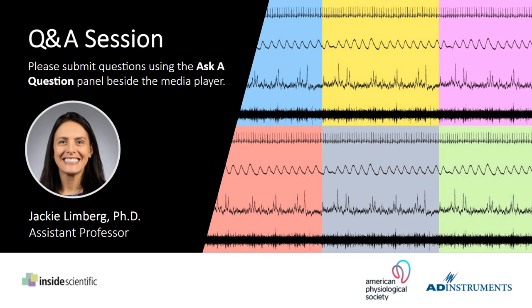Oh, for example, for heart rate variability, I know a lot of people use them. I think the importance is if you're going to use it and trust the data from it, you should know your sampling rate, because depending on the equipment, if your sampling rate is under 200 hertz, you should be concerned about the reliability of your data. Same thing if your signal's filtered or if you're just getting a black box set of numbers from it.